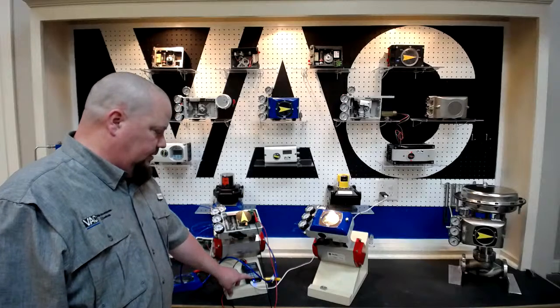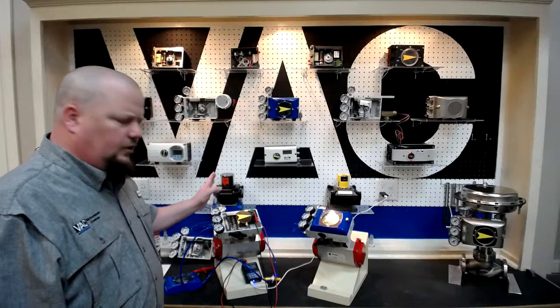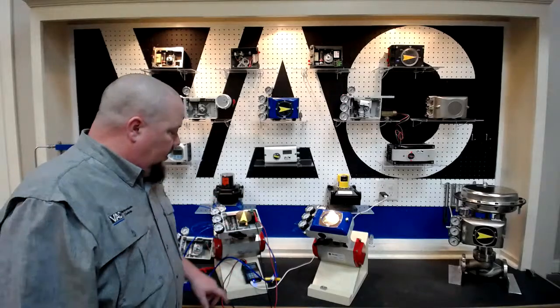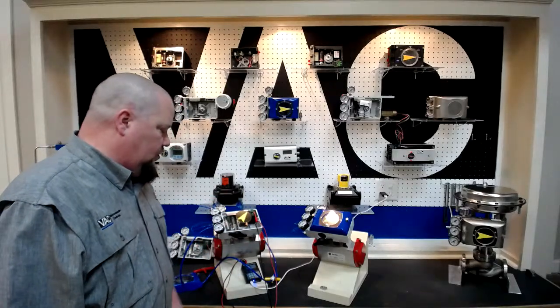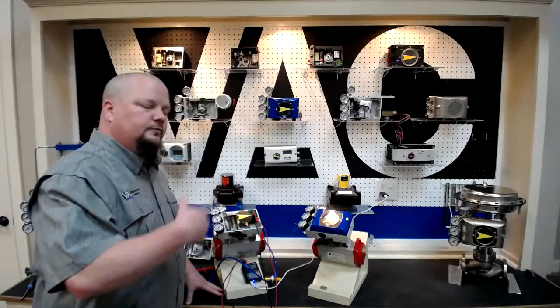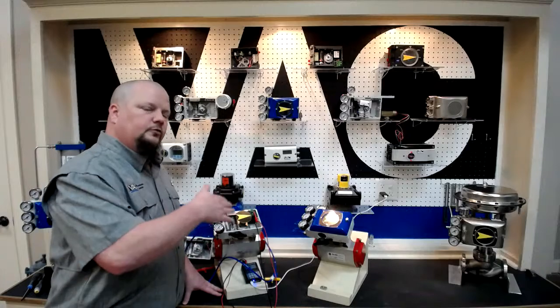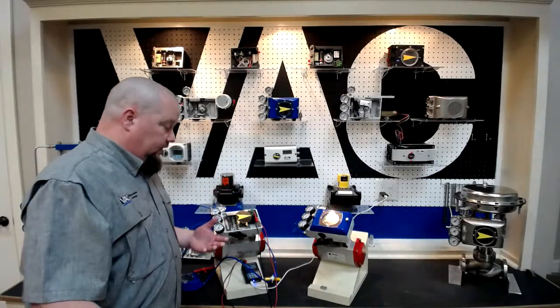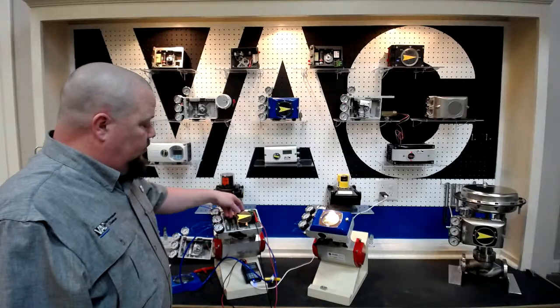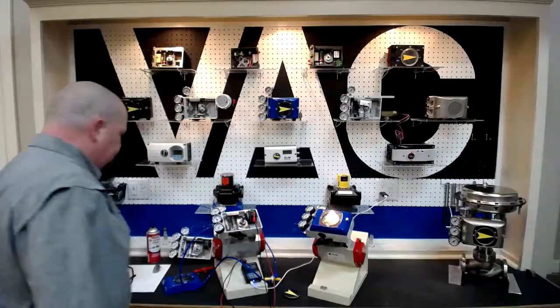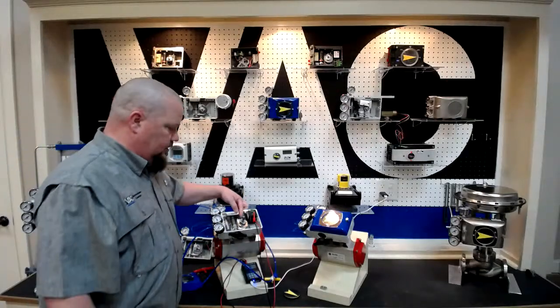We're at 12 milliamps coming down, 4 milliamps coming down, and notice it doesn't act quite properly. You're getting almost full stroke, but not quite. But you see that we don't get that fluid, smooth action from 4 to 20 milliamps. It doesn't ramp up, and it's not a linear curve as we'd like to see. So we know that initially what we have to look at is our cam setup is an issue.